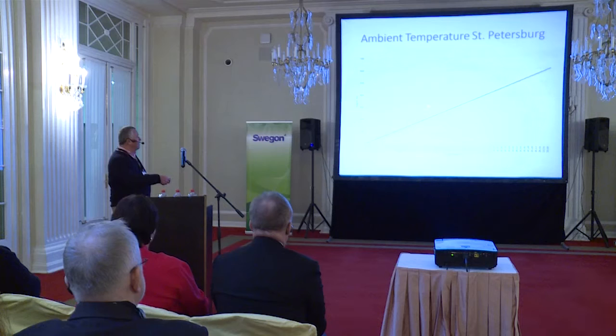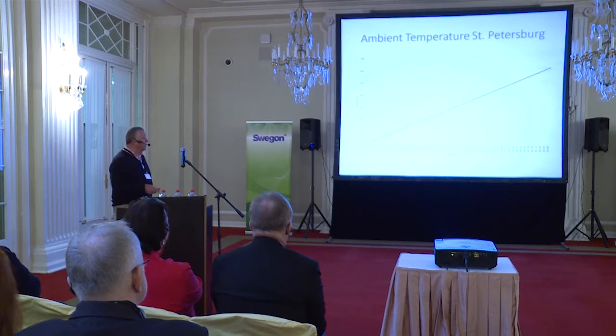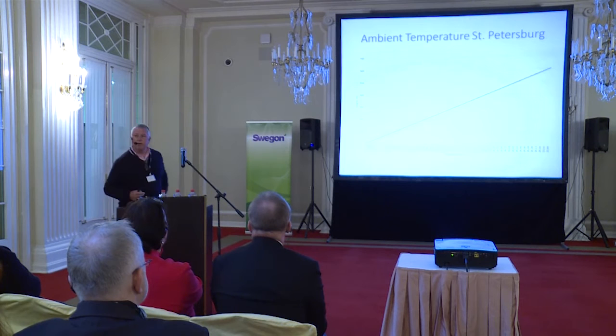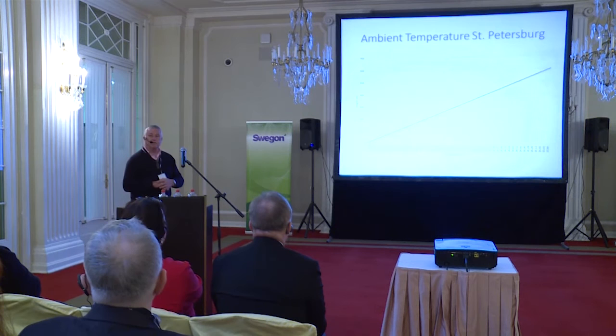But as we start to go up, 100 meters, 300 meters, which is super tall, and up to 600 meters, which is mega tall, the temperature reduces. So when we do load calculations, we have to start splitting the building up into segments and correcting each one for the different load calculations.